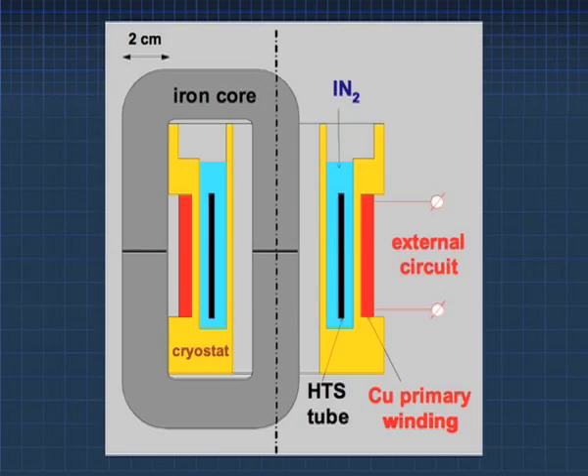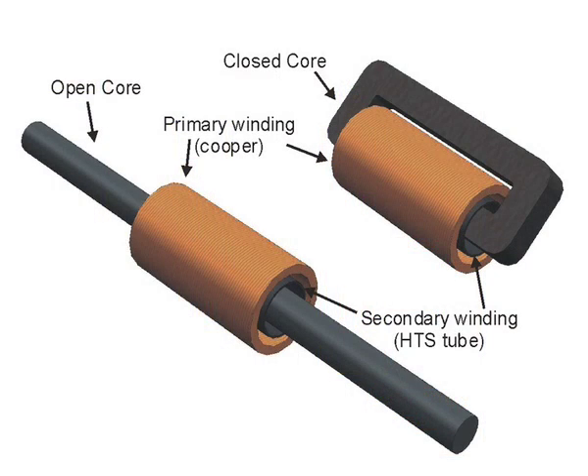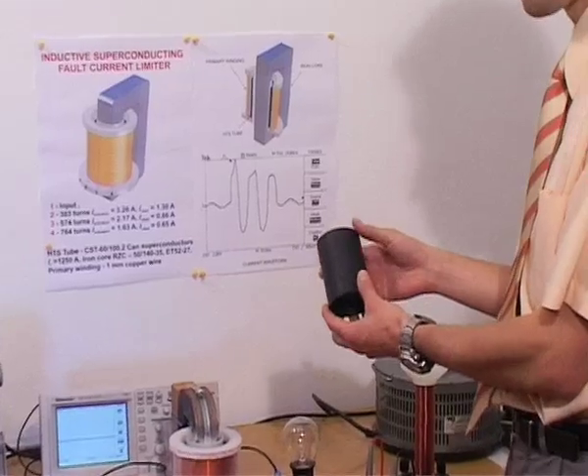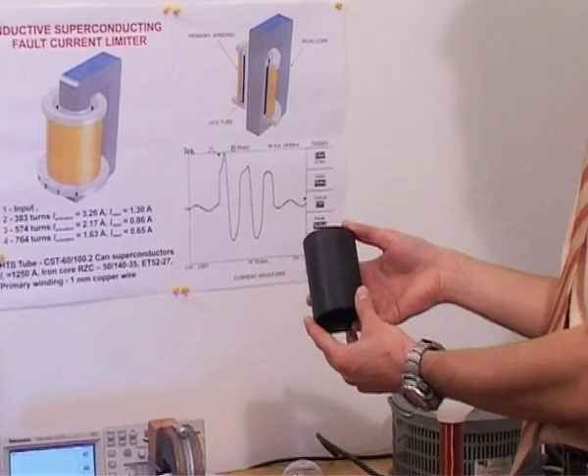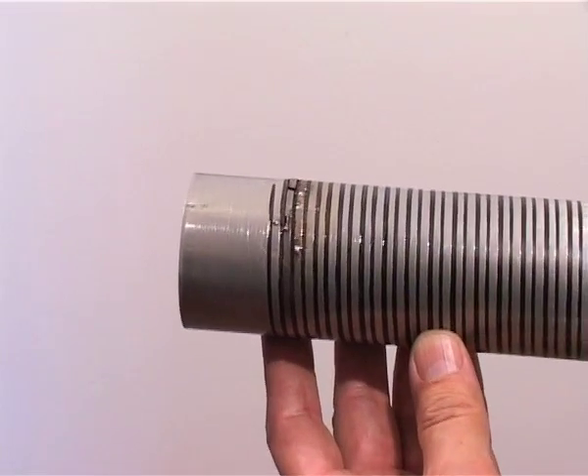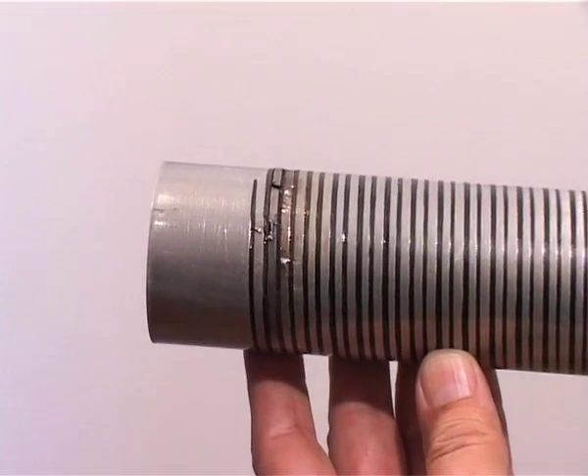The disadvantage of the inductive limiter is the large amount of iron and the very awkward nature of the cylindrical inductor. The advantage is that there are no current contacts to it, which cause losses in the resistive limiter, and also that hot spots in a cylinder are bypassed by the rest of the cylinder, whereas resistive fault current limiters are very vulnerable to hot spots.